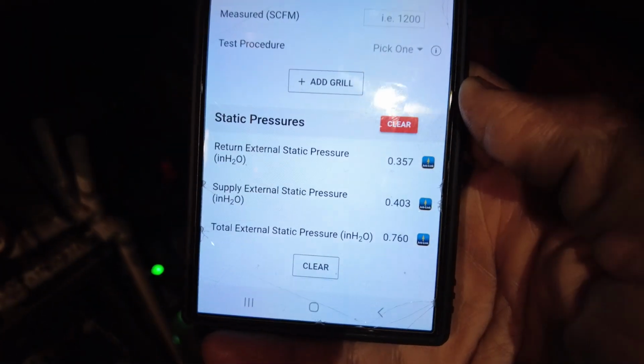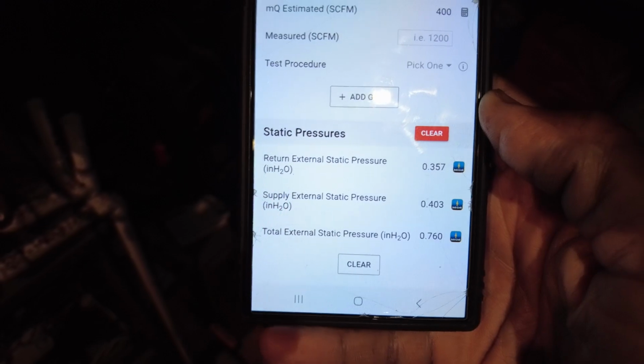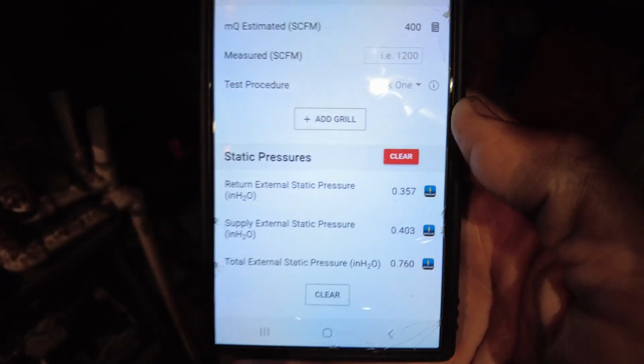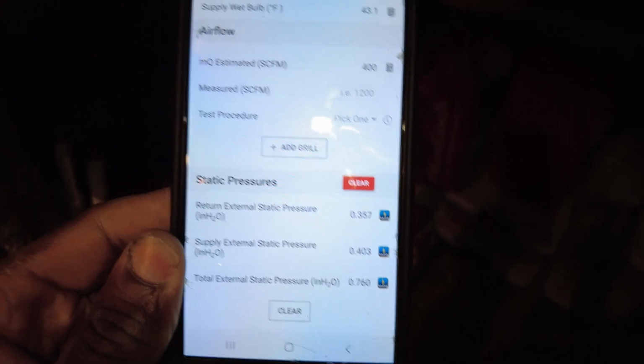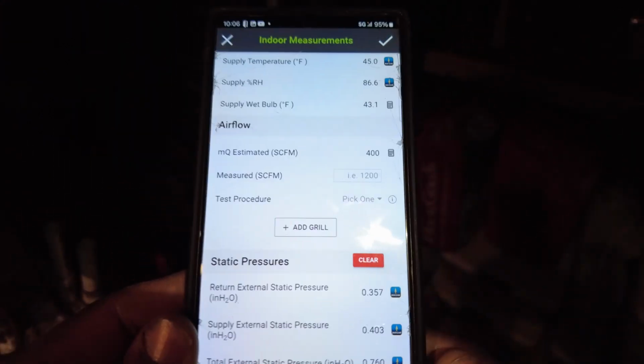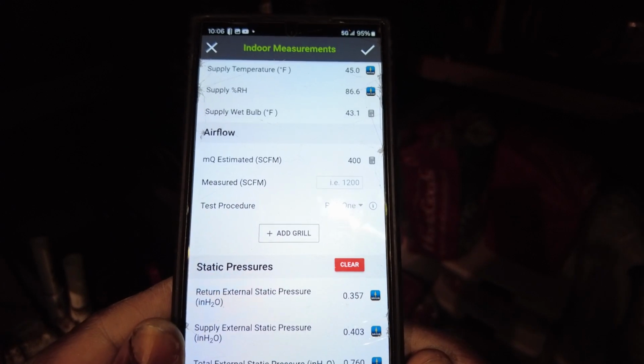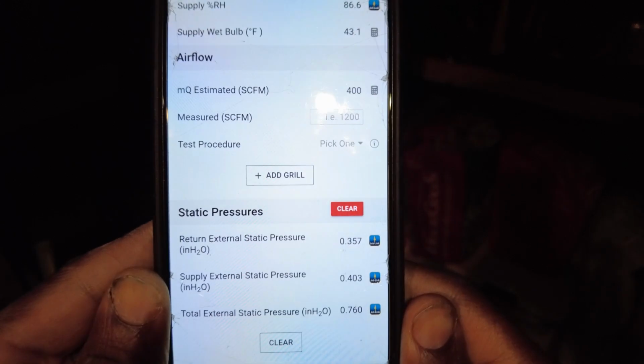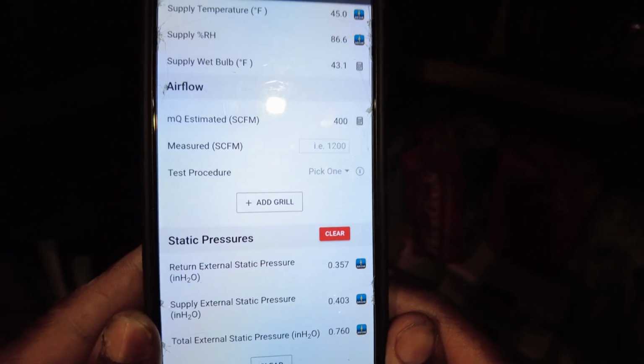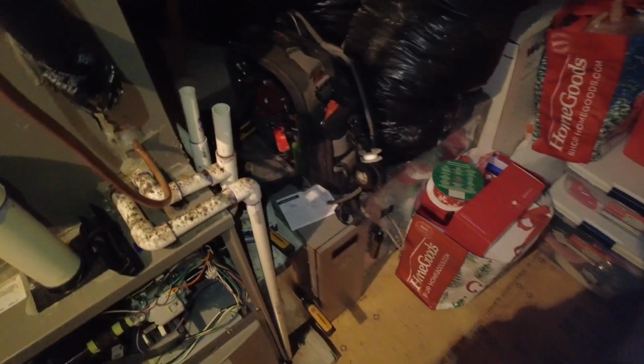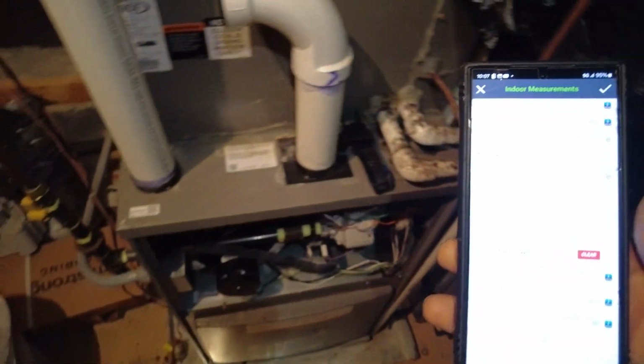as usual with zone systems, right? It's nothing new. So we got a 0.4 on the supply. Okay, but yeah, if we can get that return down nicely, I have a feeling our airflow is set pretty low as well. If we can get that return down to like a 0.2, that'll get us to a 0.5, like a 0.6 or so, with both zones open. But yeah, we might even be able to get a little lower than 0.2, but that's pretty much it. Let me see if we can, and what that's going to do as well, that's going to hit two birds with one stone.